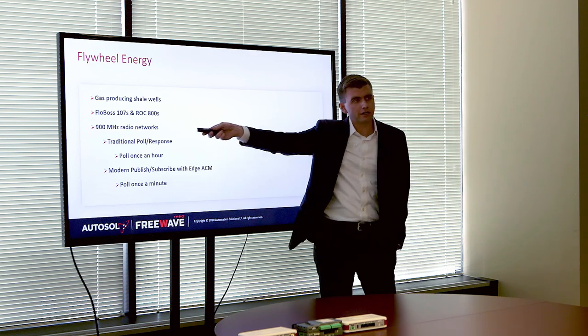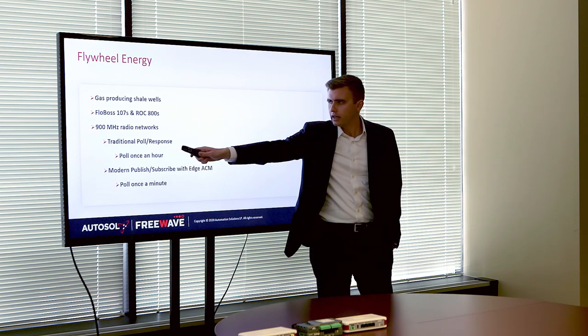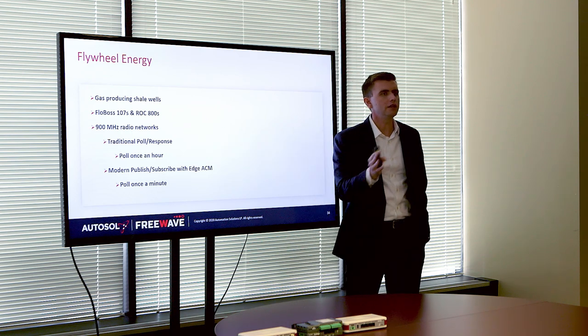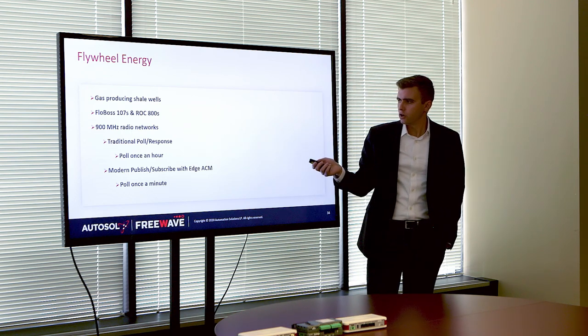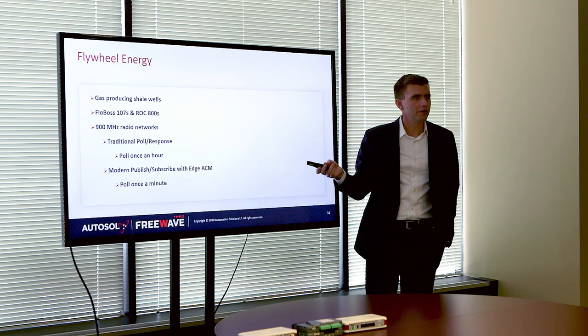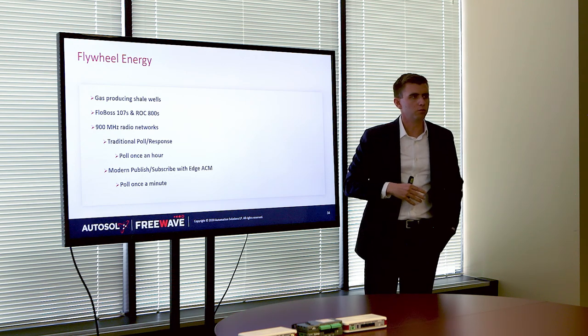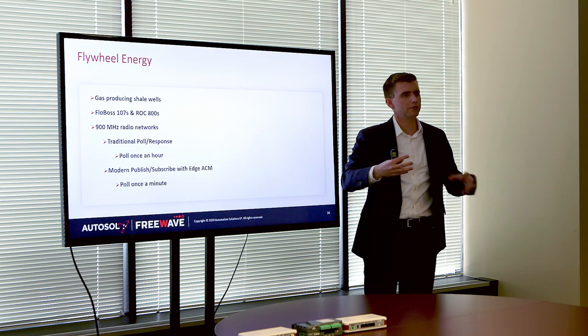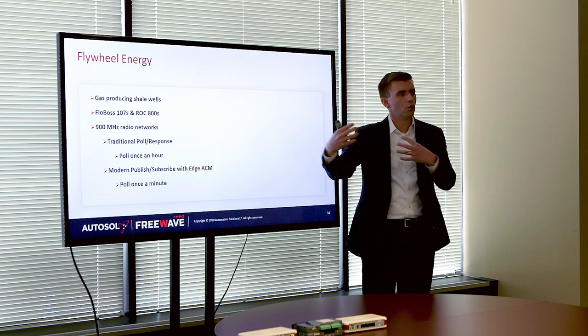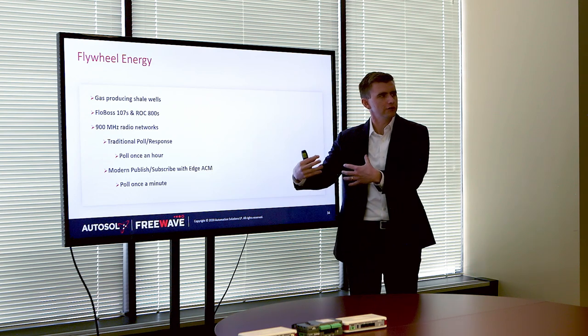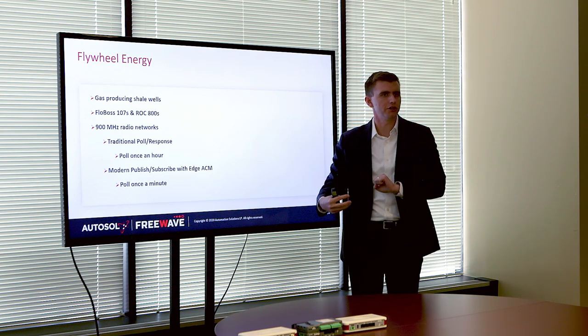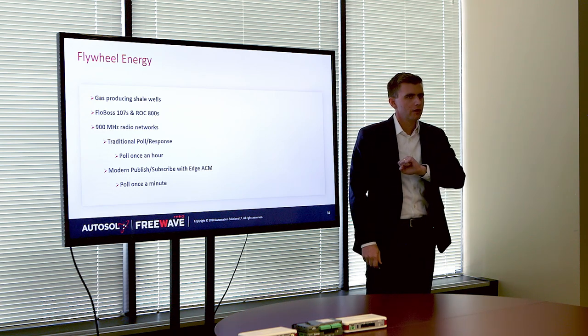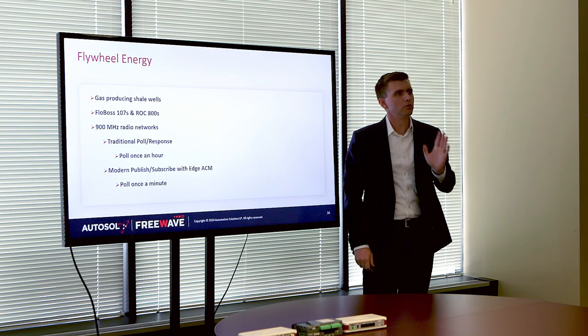Flywheel made use of that technology on about half of their devices, still using 900 megahertz radio with the ZoomLink. They were polling once an hour on their traditional SCADA before they had Edge ACM. When they deployed Edge ACM, one tag group focused on high-resolution polling of the five points on the plunger lift, the other tag group handled all the other points. For the tags they cared about, we got one-minute data instead of one-hour data — 60 times the data resolution for the tags that needed optimization.